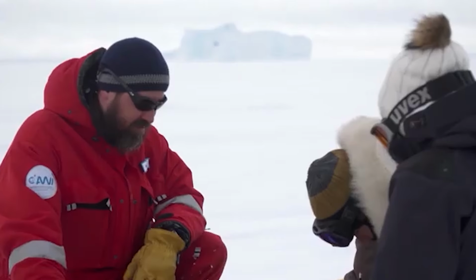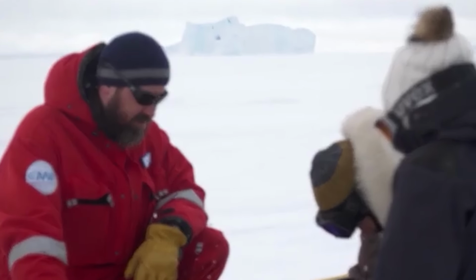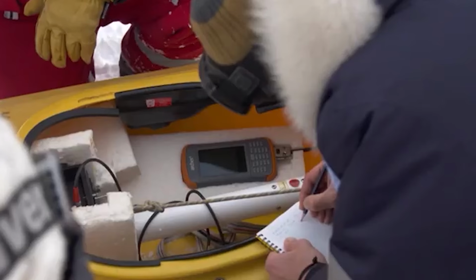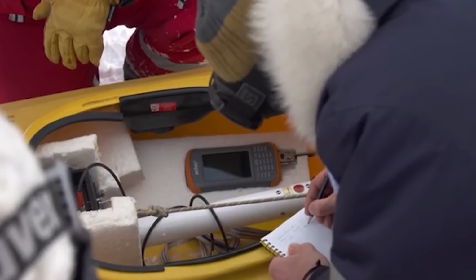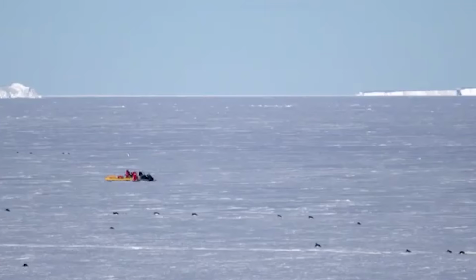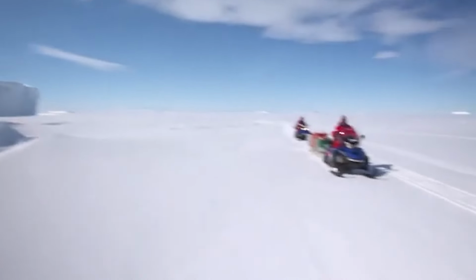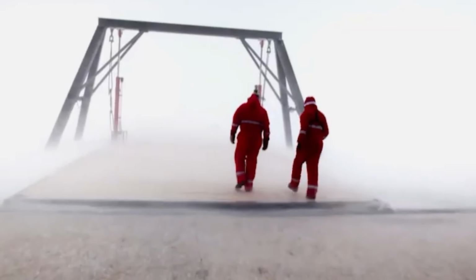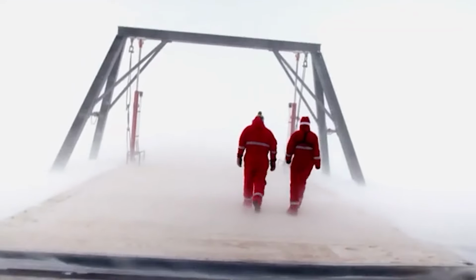But the generators do more than power block heaters. They're part of a system called combined heat and power. Industrial diesel generators are inefficient. Most of the energy in the fuel doesn't become electricity. It becomes waste heat. Normally, that heat is vented into the atmosphere and lost.